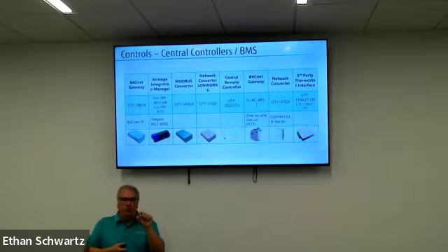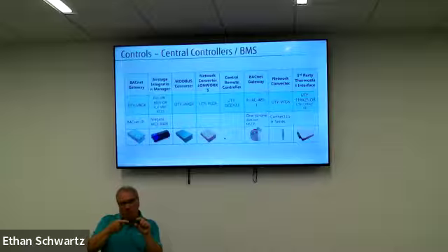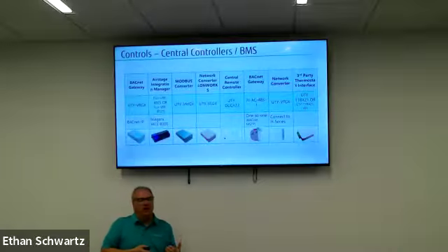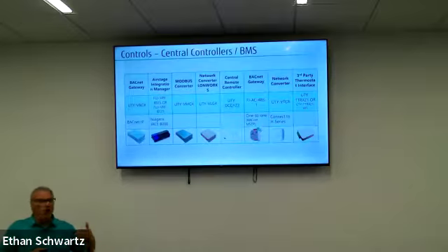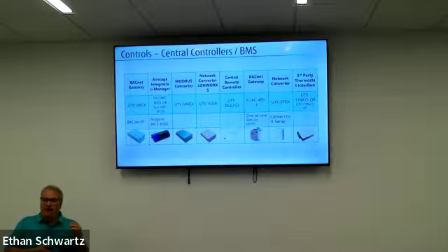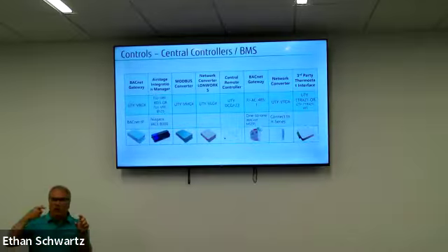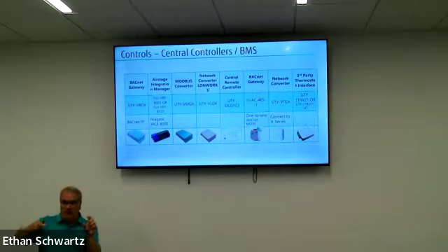Because you get more choices with those dip switches, such that you get closer matching up to what this standalone third-party thermostat is reading. Remember that in a structure, the load is always variable. Maybe it just needs a little bit of that compressor speed to maintain that temperature. But when you have a snap-acting thermostat, a true thermostat that just says, hey, I'm above 72 or I'm below 72, when it says I'm above 72, that goes into our controller. Maybe I'm a degree above 72. That call for cooling on our end can be chosen to be a 68-degree set point. It goes to the indoor unit.